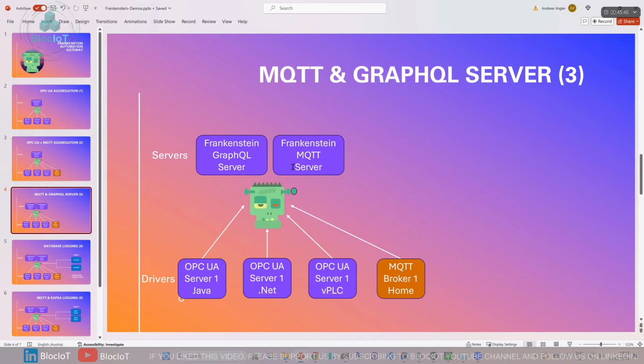No, that's not the case. This MQTT server has the MQTT server interface, so a client connects to it, and when it subscribes to a topic, the gateway will subscribe to the source topic in the right OPC UA server and then pass through the data. That means if no client is connected here, then no data is fetched from any OPC UA server. That's very important.